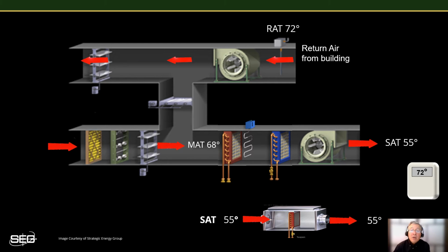So far, so good. But now let's take a look at the heating and cooling coils in this system. We can see that the hot water valve is commanded closed, being at 0%, and then that the chilled water valve is commanded to 70% open. Yet this all seems reasonable since the supply air temperature is showing 55 degrees and it's right at set point for this example. But we're in luck with this system because it has an additional sensor just after the heating coil that allows us to demonstrate an important point. When we look at the temperature of that sensor, we see it's reading 74 degrees. Yet we have a mixed air temperature of 68 degrees. So why is there a 6-degree temperature rise across the heating coil while the heating valve is commanded completely closed?